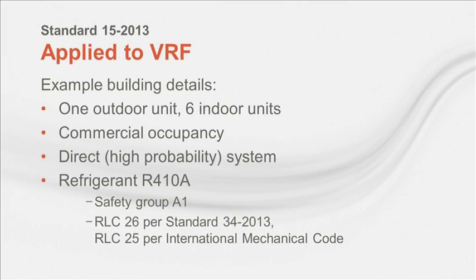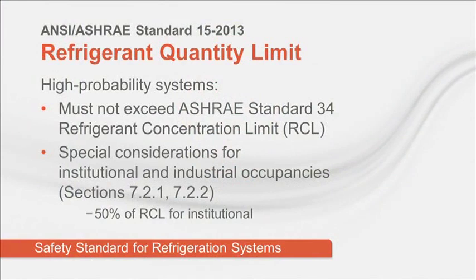Standard 34, 2013, categorizes R410A as an A1 refrigerant with an RCL of 26. However, the current version of the International Mechanical Code lists the RCL at 25. This is an example of the code being out of sync with the current standard. For high probability systems, the calculated concentration of refrigerant must not exceed the RCL for all occupancies except institutional and industrial. For institutional occupancies, RCL values are reduced by 50%. Conversely, amounts exceeding the RCL are permitted in industrial occupancies if certain conditions are met.